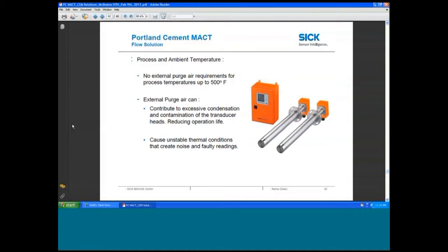The other thing that's really important to avoid when you're measuring with ultrasonics is if you can avoid the use of external purge air, it's very beneficial to the accuracy and overall operation of the system. There's really 2 main points to consider concerning this purge air. One is if you're blowing cold air from the outside across the hot face of a transducer, you can certainly see where you could start forming condensation and the possibility of acids forming and contamination of the transducer. The other thing that happens is you create unstable thermal conditions across the face of the transducer, which create noise and lead to inaccuracies and those kind of things. So eliminating that external purge is really beneficial from a maintenance and an accuracy standpoint, and we can supply these with no purge air up to process temperatures about 500 degrees F.